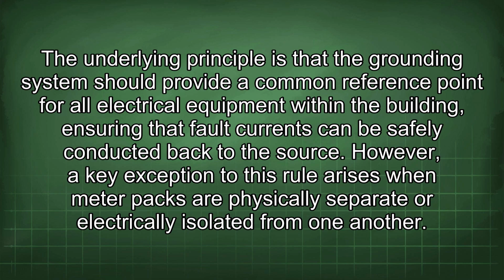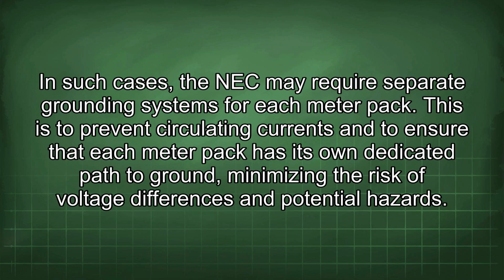However, a key exception to this rule arises when meter packs are physically separate or electrically isolated from one another. In such cases, the NEC may require separate grounding systems for each meter pack. This is to prevent circulating currents and to ensure that each meter pack has its own dedicated path to ground, minimizing the risk of voltage differences and potential hazards.